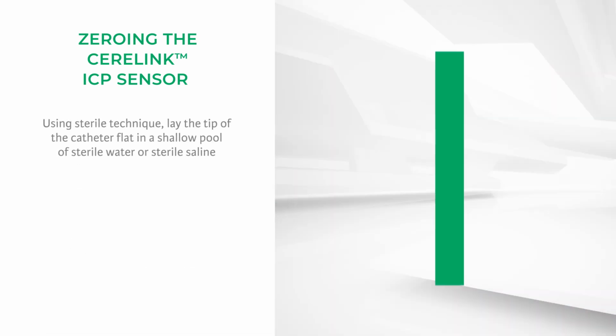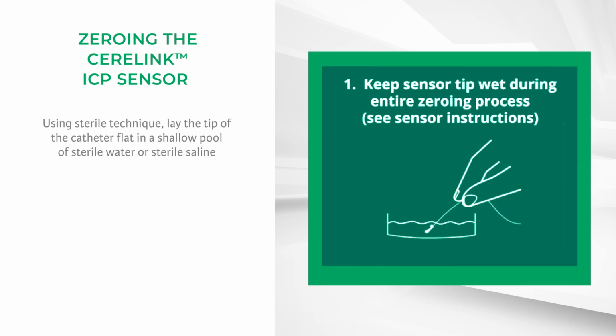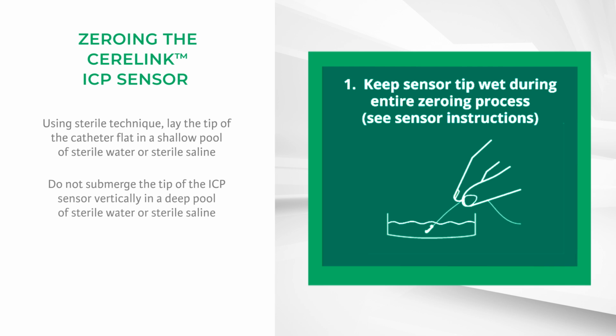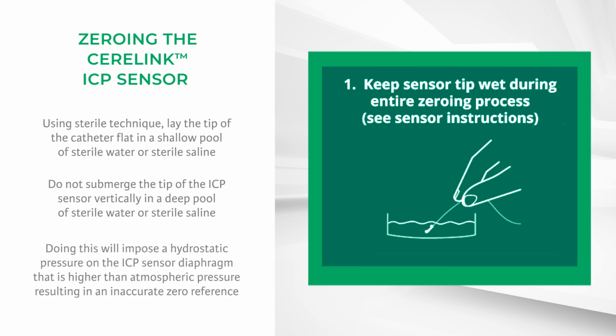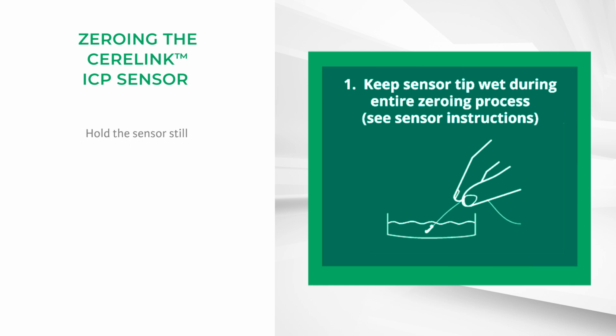Using sterile technique, lay the tip of the catheter flat in a shallow pool of sterile water or sterile saline. Do not submerge the tip of the ICP sensor vertically in a deep pool of sterile water or sterile saline. Doing this will impose a hydrostatic pressure on the ICP sensor diaphragm that is higher than atmospheric pressure, resulting in an inaccurate zero reference. Hold the sensor still.